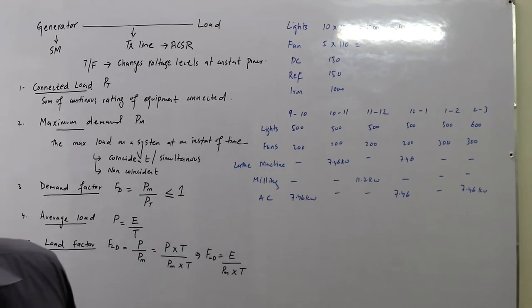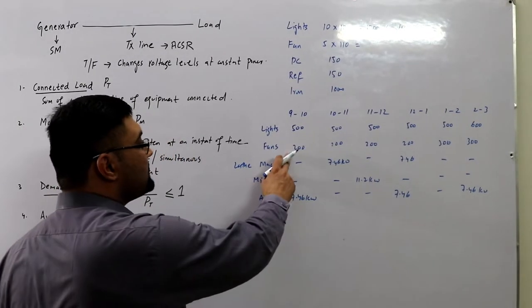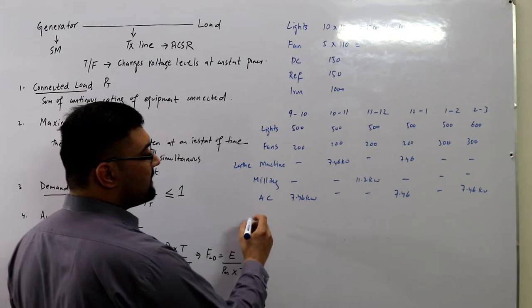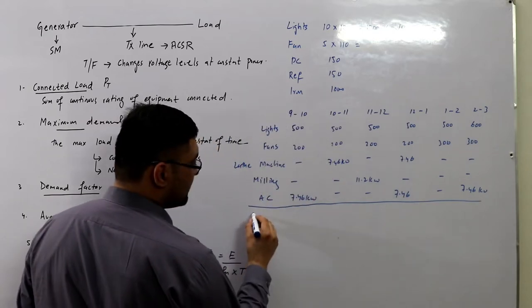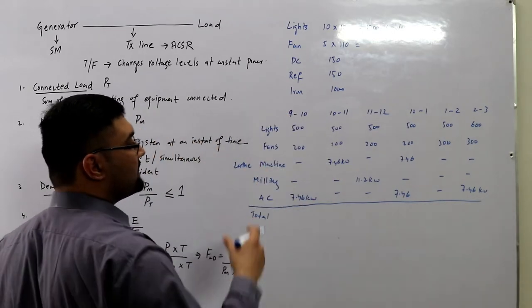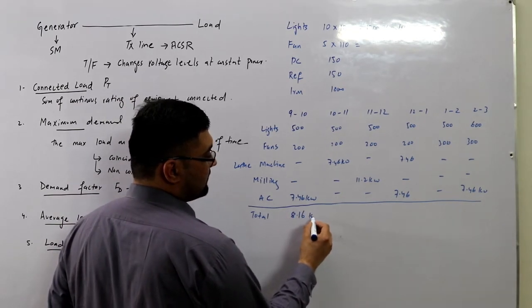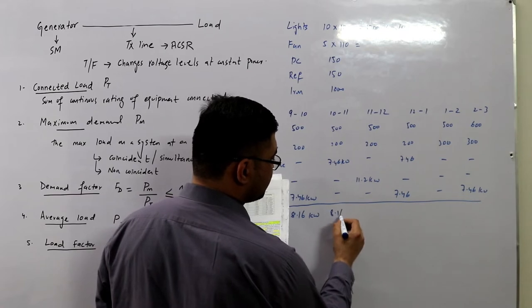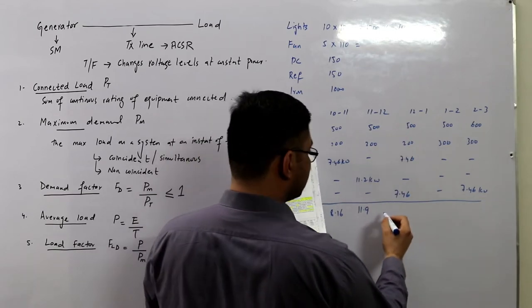Reading from the load pattern table: from 9 to 10, lights use 500 W, fans 200 W, and the AC or air compressor 7.46 kW — total 8.16 kW. From 10 to 11 the total is again 8.16 kW. From 11 to 12 the total rises to 11.9 kW. The next interval gives 15.6 kW, and the following one reaches 19.56 kW.